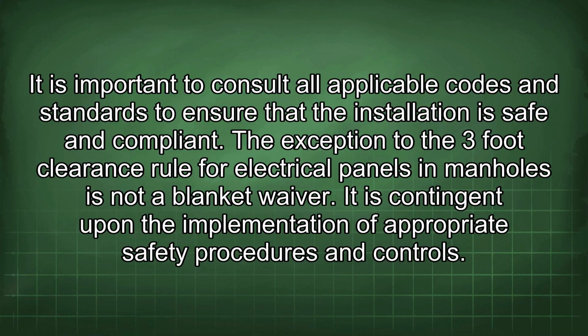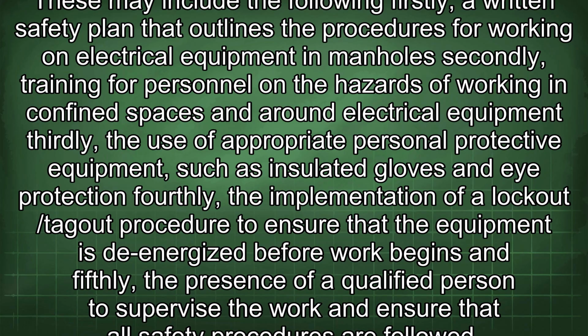The exception to the 3-foot clearance rule for electrical panels in manholes is not a blanket waiver. It is contingent upon the implementation of appropriate safety procedures and controls. These may include the following: firstly, a written safety plan that outlines the procedures for working on electrical equipment in manholes. Secondly, training for personnel on the hazards of working in confined spaces and around electrical equipment. Thirdly, the use of appropriate personal protective equipment, such as insulated gloves and eye protection. Fourthly, the implementation of a lockout/tagout procedure to ensure that the equipment is de-energized before work begins. And fifthly, the presence of a qualified person to supervise the work and ensure that all safety procedures are followed.